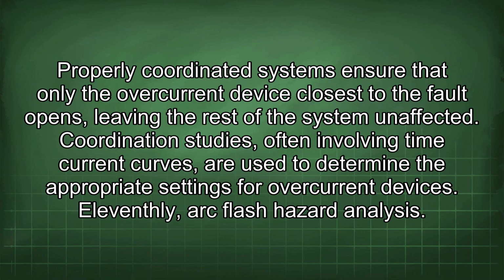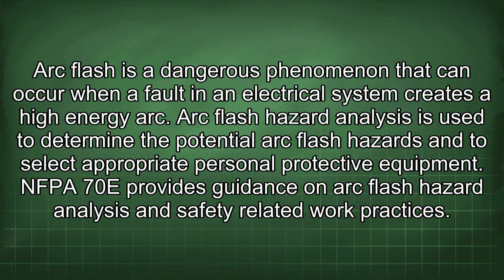11thly, arc flash hazard analysis. Arc flash is a dangerous phenomenon that can occur when a fault in an electrical system creates a high-energy arc. Arc flash hazard analysis is used to determine the potential arc flash hazards and to select appropriate personal protective equipment. NFPA 70E provides guidance on arc flash hazard analysis and safety-related work practices.